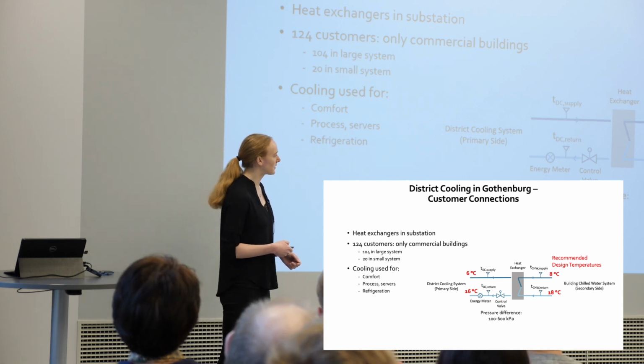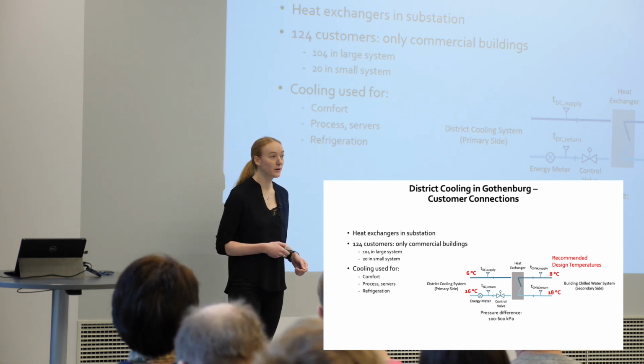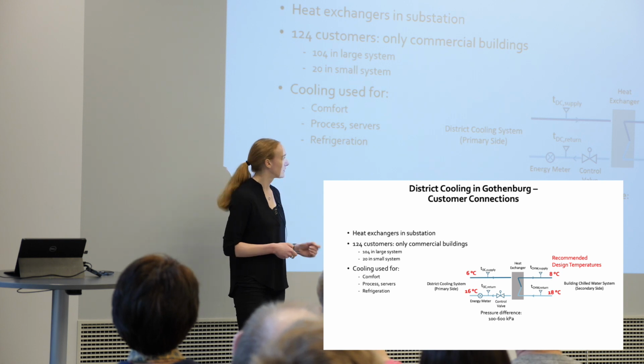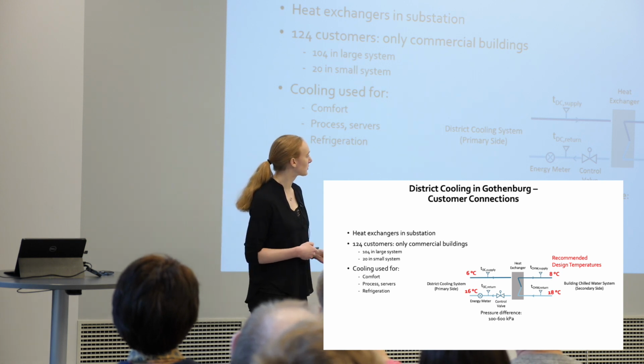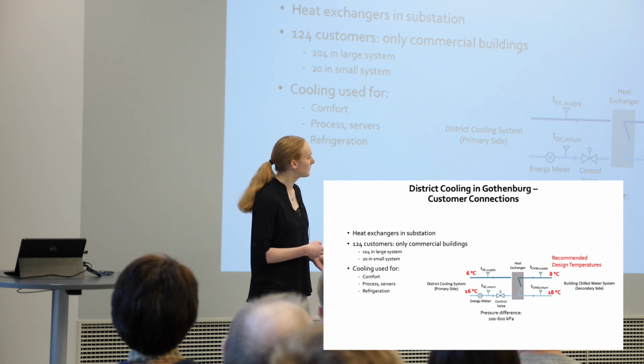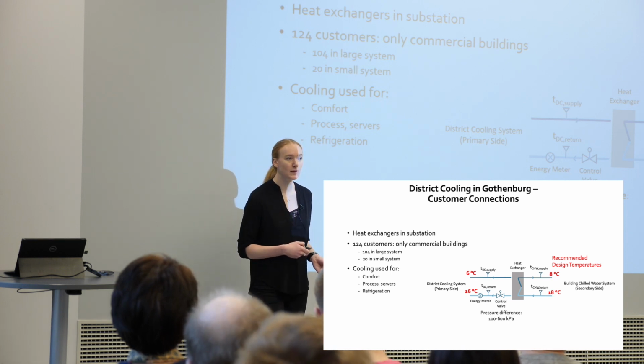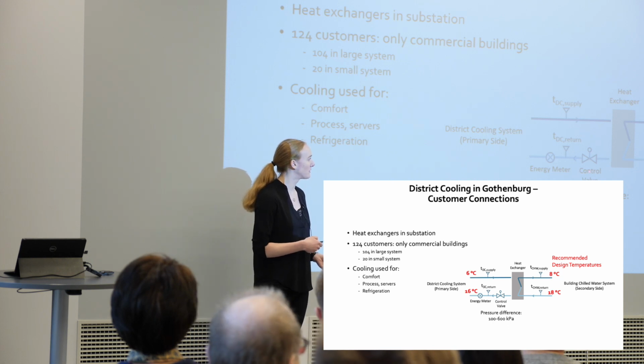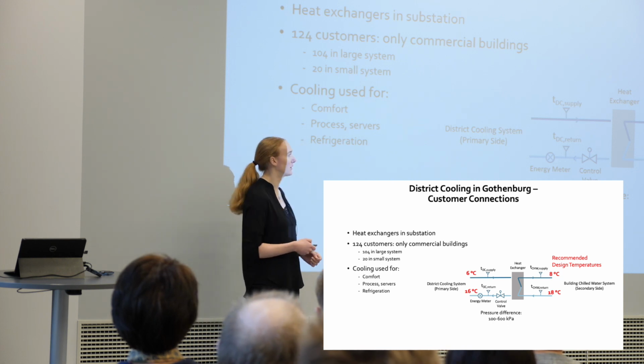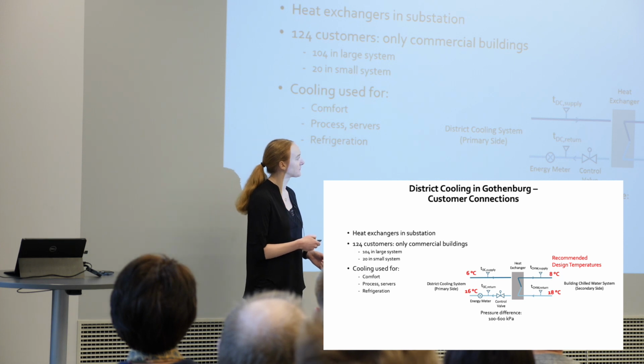The pressure difference across the control valve is between 100 and 600 kilopascal, so it's quite a large range they have to control over. And it is the building management system that controls how much this control valve should open and close depending on what the cooling demand is in the building.